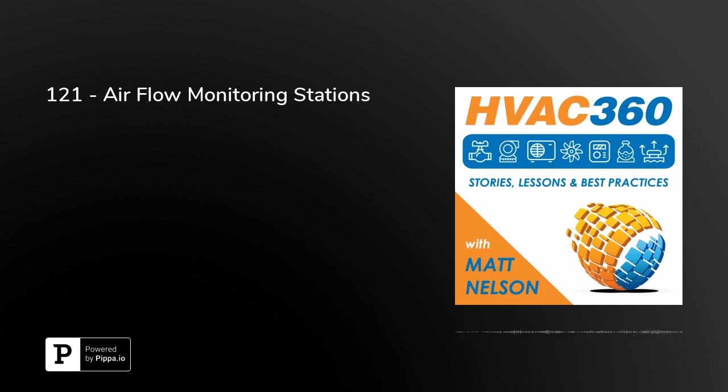They're very touchy. They can have a lot of back and forth. So really nail this down. If you're using the airflow monitoring stations as a point in your control sequence, so it's controlling something specific, whether it be a damper or whether it be fan speed, be very careful because it can go very wrong. That's one of the lessons learned that I'll talk about a little bit later.